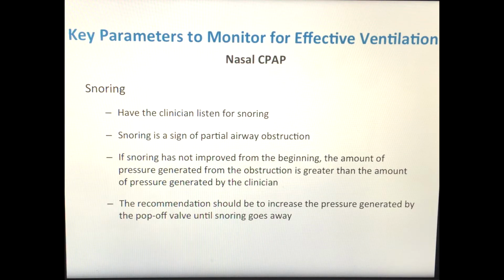If the snoring is a little bit softer, but not completely gone, you then want to advise the clinician to increase the amount of pressure being delivered by adjusting the pop-off valve, maybe from 10 centimeters to either 15 or 20 centimeters of water pressure. Obviously, the more pressure that is being generated into the patient's nasal pharynx, the more the walls of the nasal pharynx will be separated and the more patent the airway.